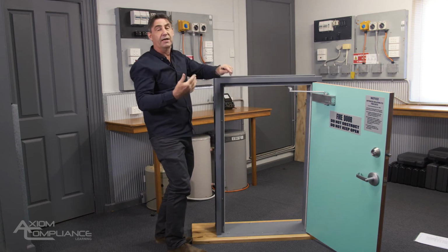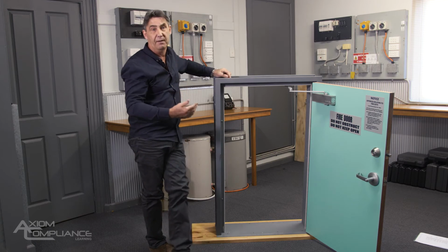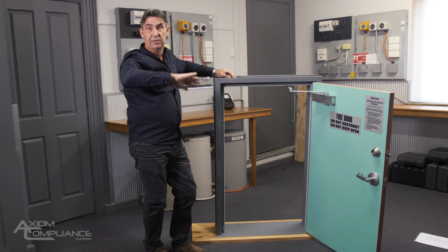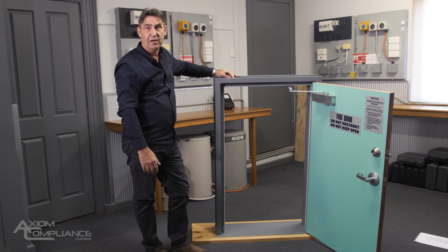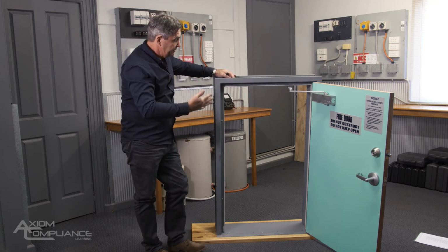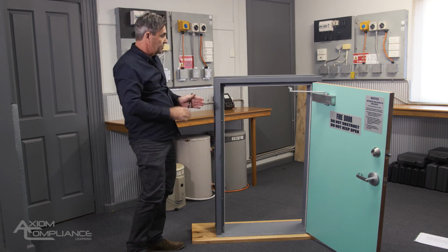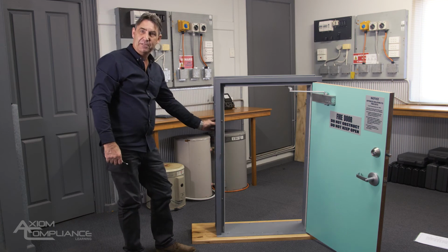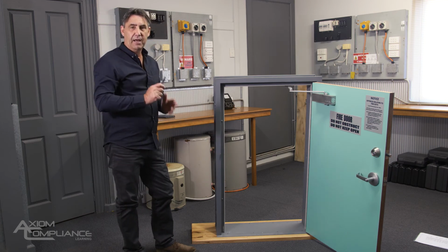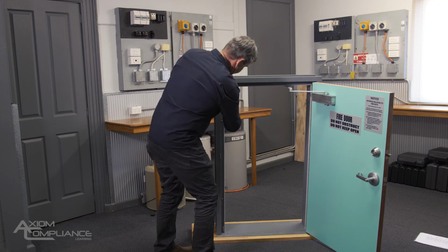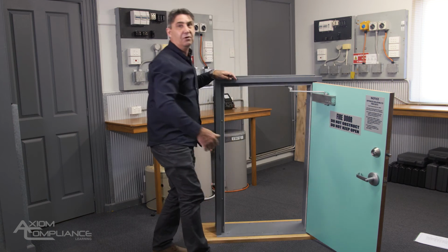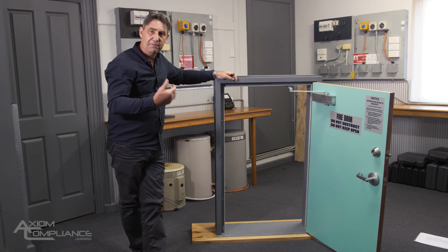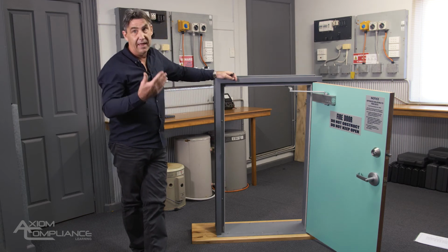A key indicator that the door frame is not a fire door frame is when you just get spot welds in the corners. You should have a completely sealed corner and edge on those frames. The other thing about the frame is you've got to make sure that the frame is core filled and backfilled. Now obviously I can't backfill this frame because it is not connected to anything, but what you do is you knock on the frame and you listen for a different sound. And if you can definitely hear a hollow sound in there, that needs to be filled.